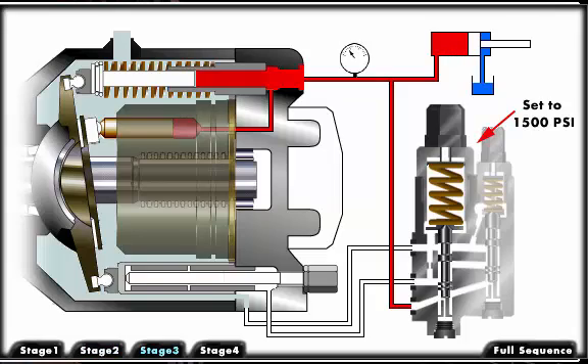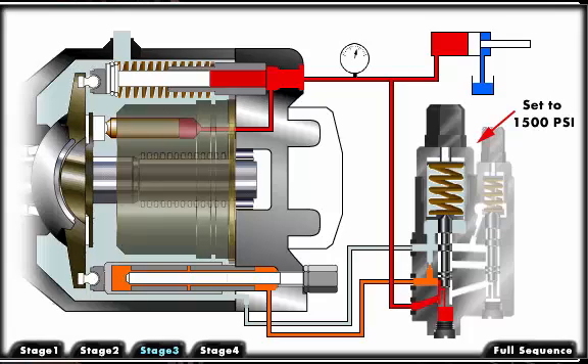When the cylinder reaches the end of its stroke, pressure rises at the outlet of the pump as the fluid's flow path is blocked. This pressure forces the compensating spool up, allowing the pressurized fluid to energize the destroking piston and push against the swash plate, forcing it to a vertical position. With the swash plate vertical, the pump is now destroked and the pressure at the outlet port is maintained at a constant level. A very slight amount of flow is produced to maintain destroke pressure, and this flow is bypassed into the case and carried back to the reservoir through the pump case drain outlet.